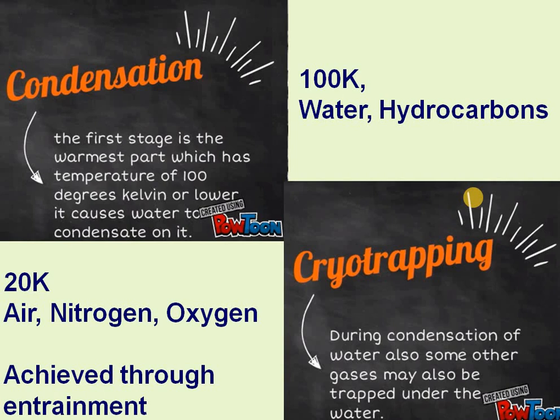Three types of physical processes are involved in a cryogenic pump: cryocondensation, cryotrapping, and cryosorption. In cryocondensation, the temperature required is around 100 Kelvin. At this stage, water vapor and hydrocarbons — oil vapors from diffusion pumps or rotary pumps — get deposited. That is simple cryocondensation: simple condensation happening at very low temperature.